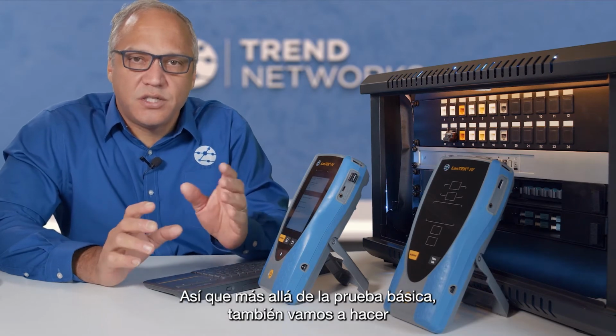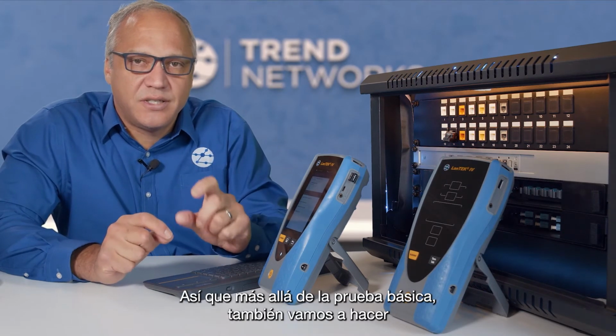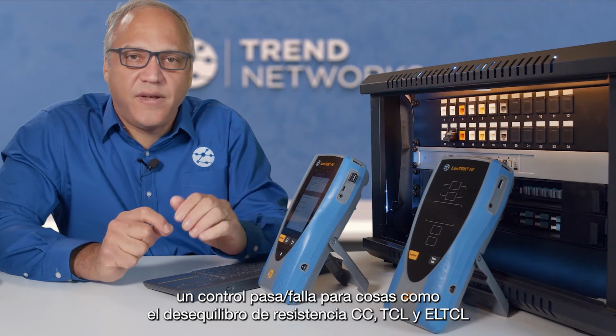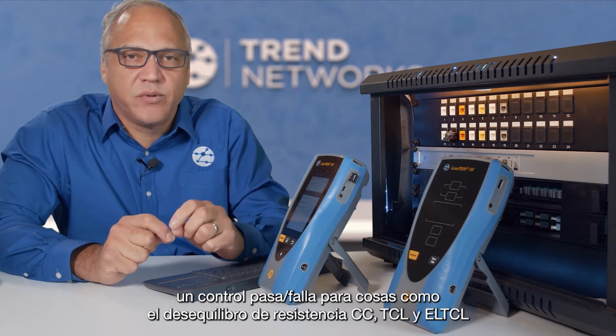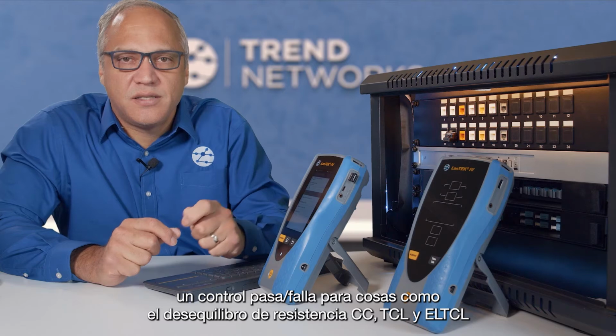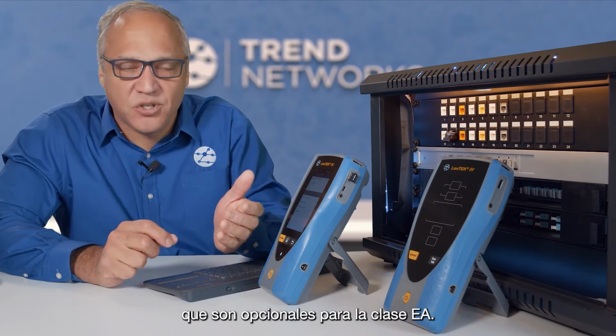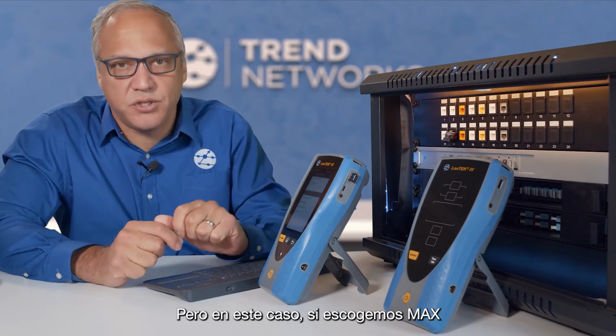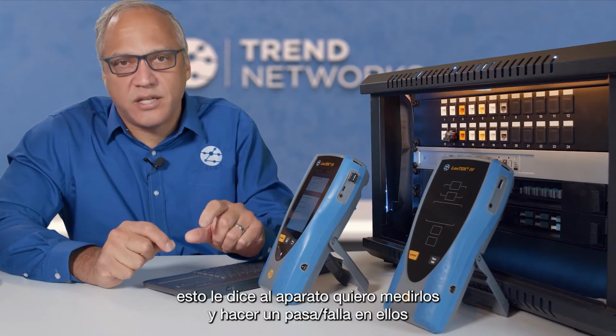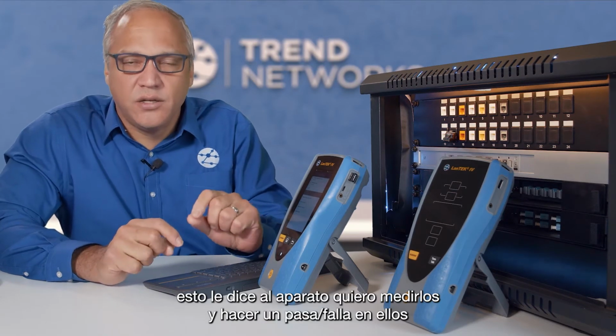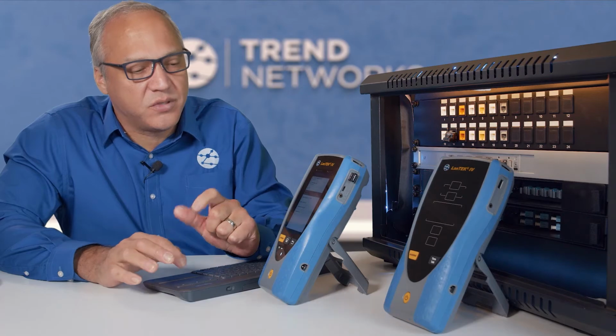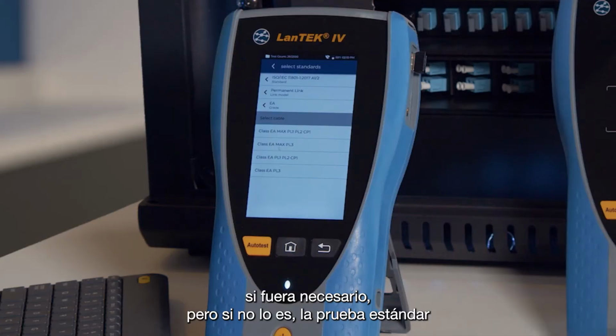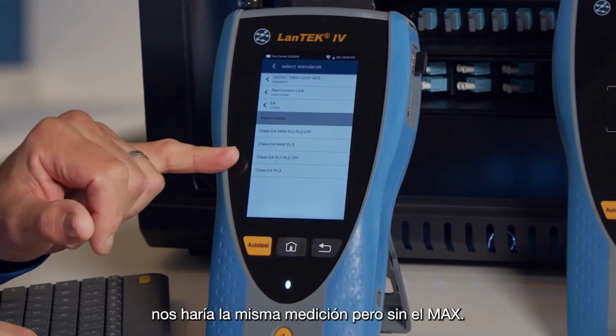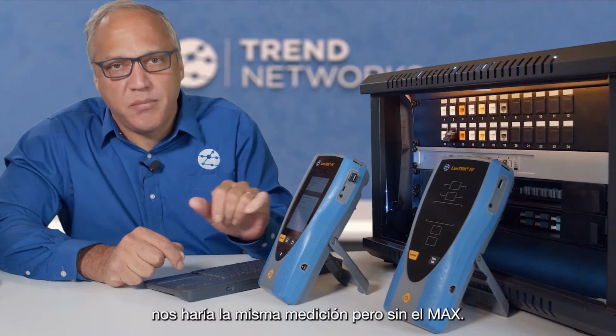So beyond just the basic minimum test, we're also going to do a pass-fail measurement for things like DC resistance unbalance, TCL, and ELTCL, which are optional for Class EA. But in this case, if we choose Max, it's telling the tester, I want to measure those and do a pass-fail result on them. So that may be a requirement. If we don't need that, the standard test would just be the same measurement without the Max.